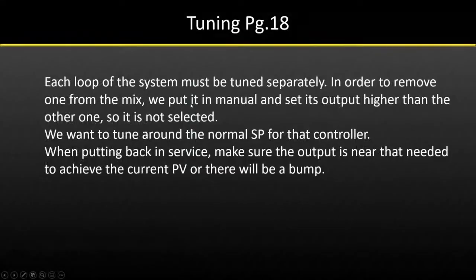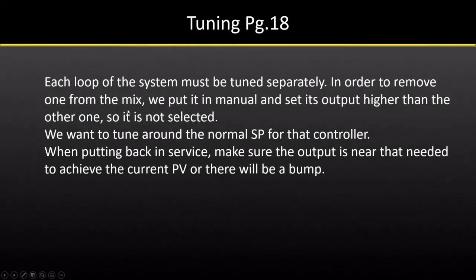Tuning: each loop of the system must be tuned separately since they don't operate together. To remove one from the mix, put it in manual and set its output higher than the other one so it doesn't get selected inadvertently. Tune around the normal set point for that controller. When putting it back in service, make sure the output is near that needed to achieve the current PV, or there will be a bump.